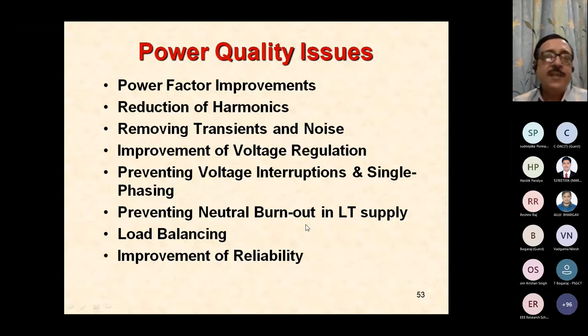Unfortunately, today the situation is entirely different. Take a case of a power electronic load like a switch mode power supply used for a desktop. Even though we balance the desktop loads on the different RYB phases, each desktop current is non-sinusoidal and there is a third harmonic component in that current. All the third harmonic components in the input current are actually zero sequence components and they will flow through the neutral only. They cannot find a return path through the lines. So therefore, the neutral current becomes unpredictably large if you put a nonlinear load, even though the loads are balanced on the phases, because of zero sequence third harmonic components.